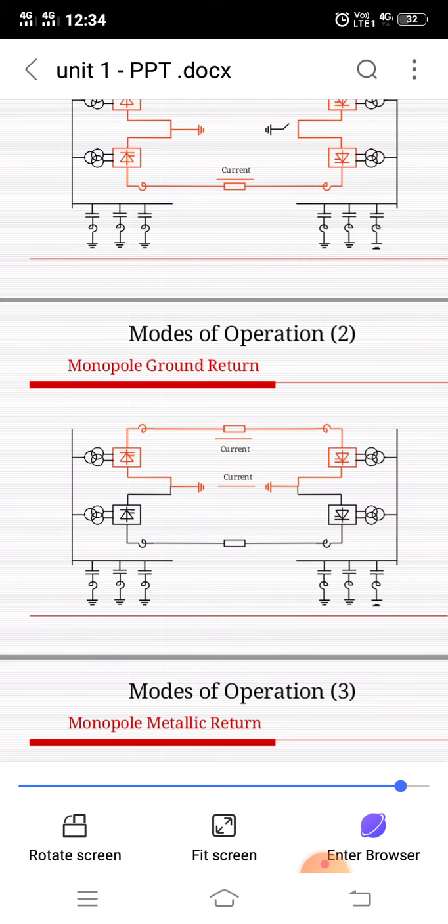Then the firing pulse has no effect because the cathode is negative. So the flow of current in a valve ends when the voltage between anode and cathode becomes negative. The instant when current begins to flow through a valve or to commute from one valve to another can be delayed by postponing the firing. This method permits the average value of the outgoing voltage of the rectifier to be changed.